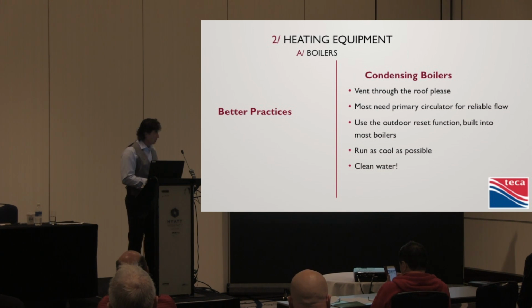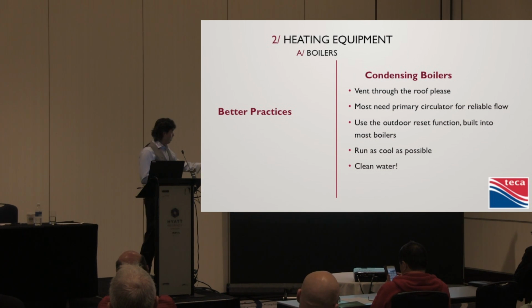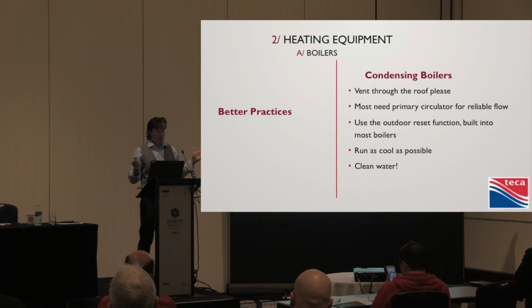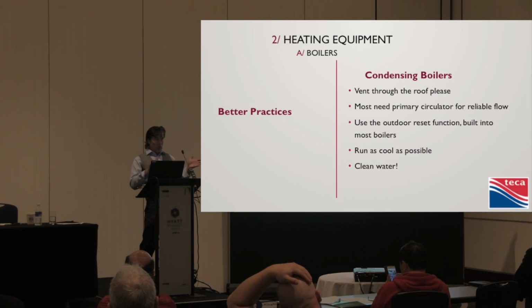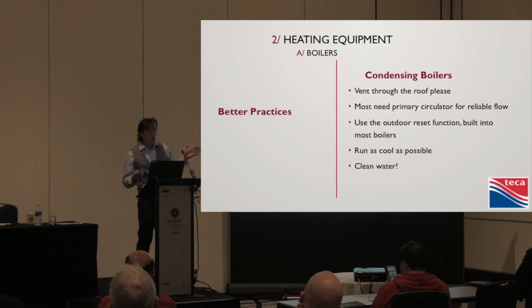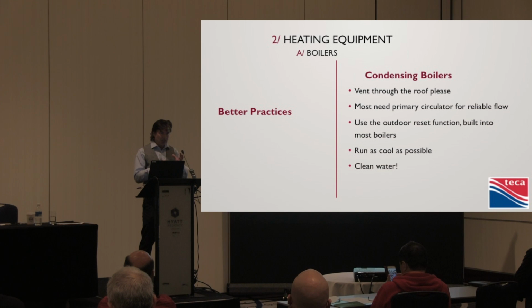Use the outdoor reset function built into the boilers. That's the other critical thing with respect to load matching we'll talk about in a few minutes, I hope. Run them as cool as possible. These things condense with a return water temperature that's below 140 F. So that's kind of tricky. Those baseboards, you know, they're 180, 190, whatever. Some of the convectors have higher supply water temperatures. Radiant floor, however, we know we're not going over, say, 130, because of our surface temperature limitation. So if we have a 15-degree temperature difference in our design, that means we're coming back with fairly cool water. So that's great. The condensing boiler loves that return water to be cold. The combustion process really condenses them.